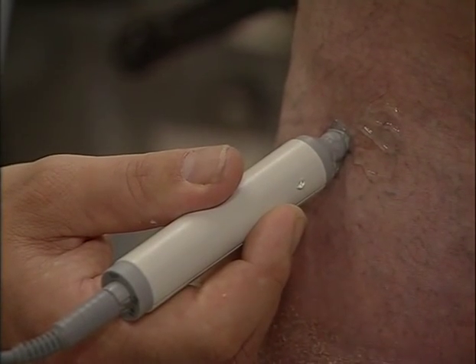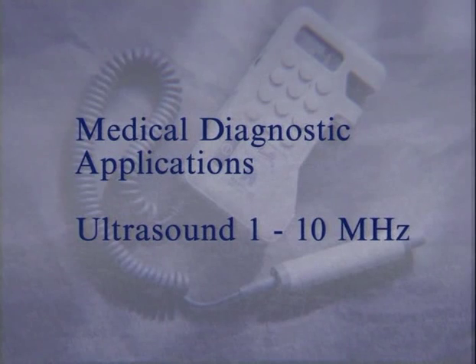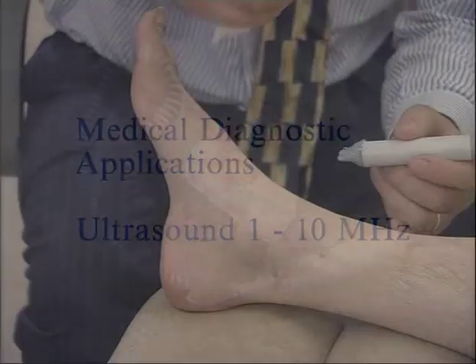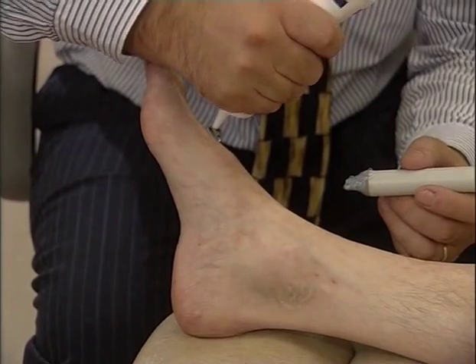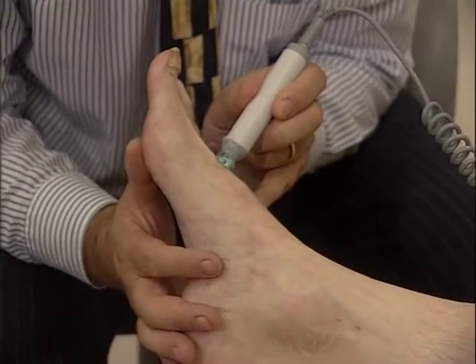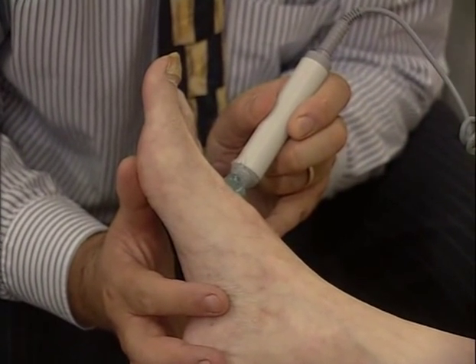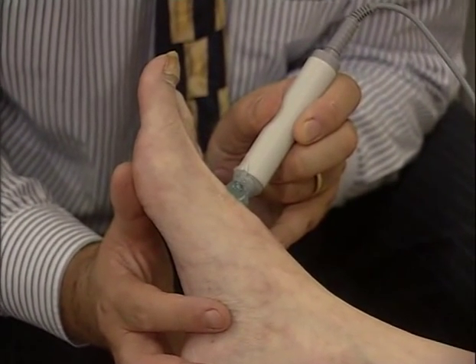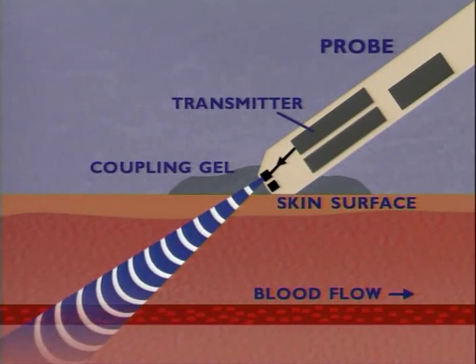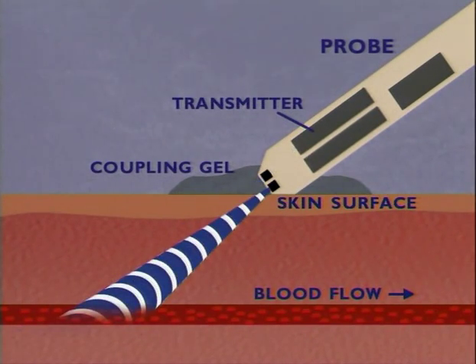Doppler probes produce ultrasound signals typically between 1 and 10 megahertz. This is outside the upper limit of the normal hearing range. Ultrasound passes easily into the body but not through air, so a water-based coupling medium is used. When the ultrasound signal encounters blood cells moving in a vessel, some of the signal is reflected at a Doppler shift frequency related to the speed of the blood cells.